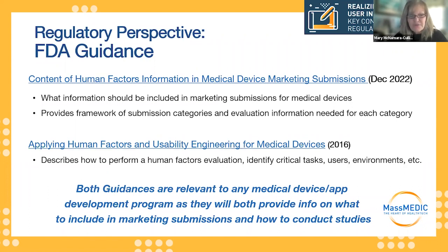So the first document provides you with a framework of what is needed in a marketing submission. The second guidance document will tell you the types of testing and human factors engineering analyses that are required. But again, I urge you to use both of these documents.